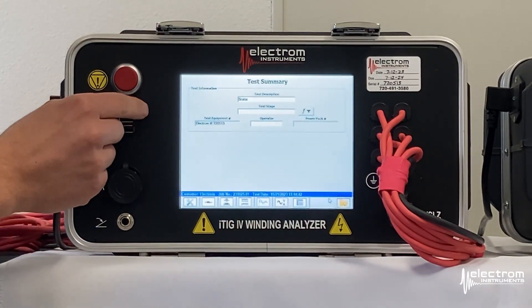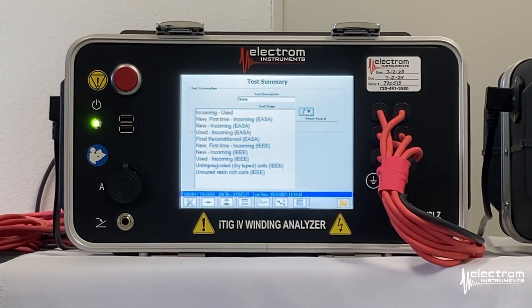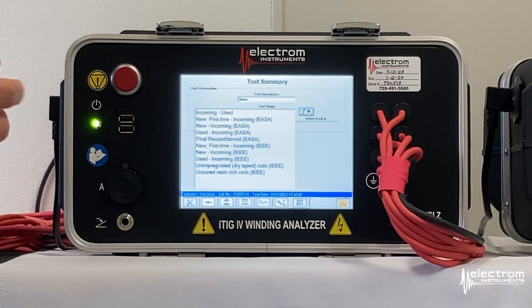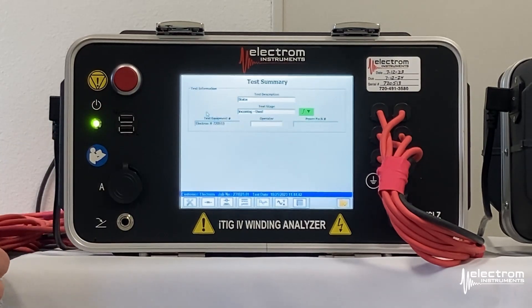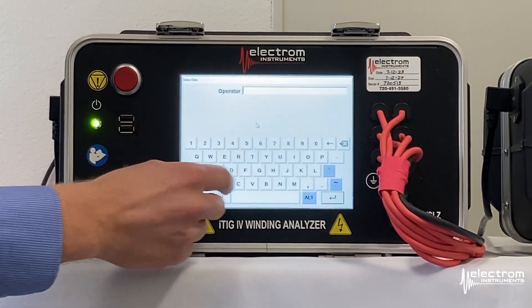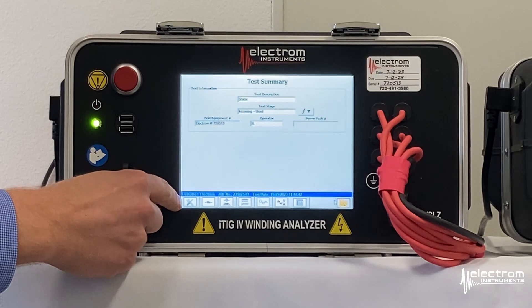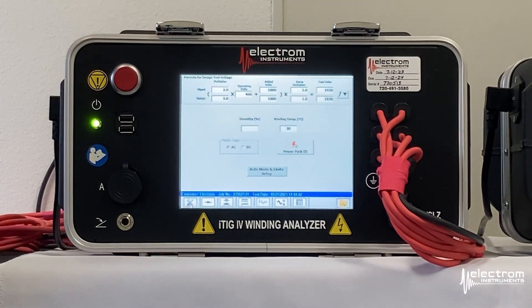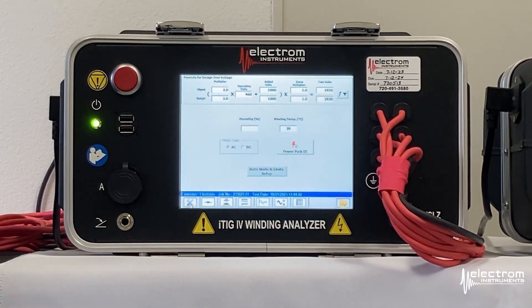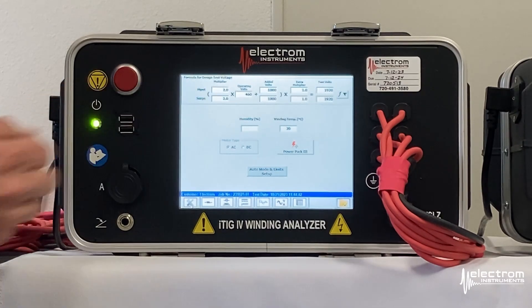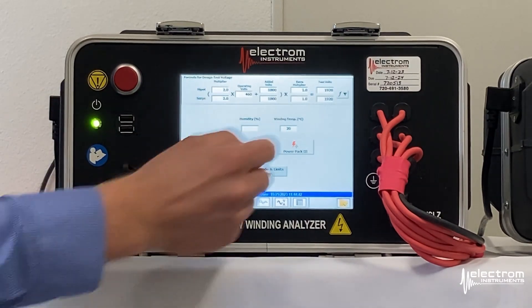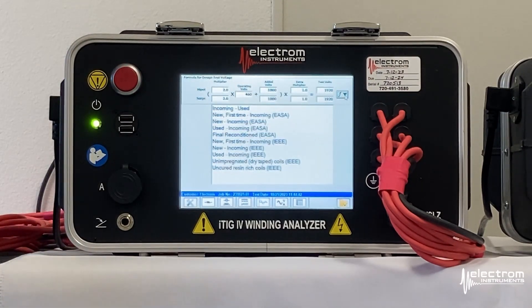Next up is the test stage. We have some pre-programmed test stages; some EASA and IEEE test stages are already in the database and these can be added to or removed. We're going to select an incoming used test stage. At the top of the setup screen you see the hypot and surge test voltage formula associated with the selected test stage — in this case it's two times the operating voltage plus 1000. You can always click any of the white fields to change the test voltage or use the function drop-down menu to select a different test stage if needed.